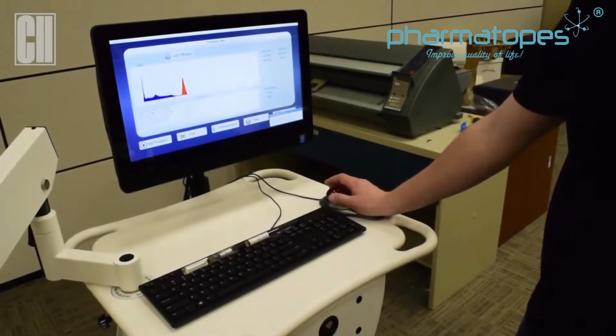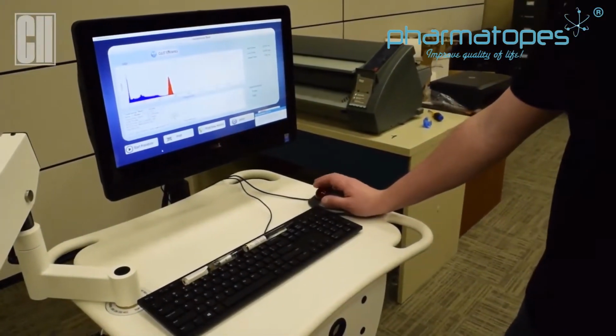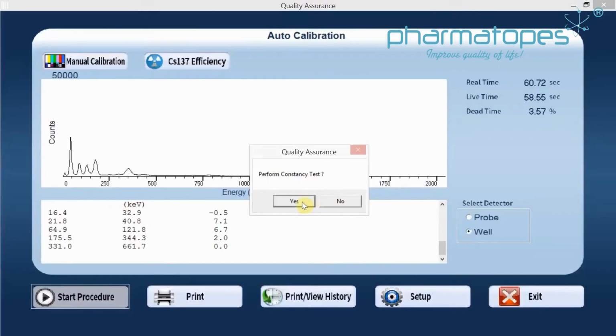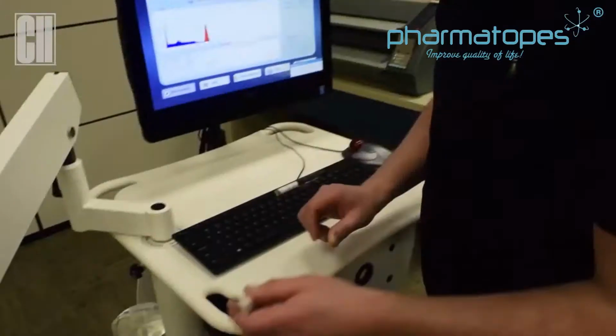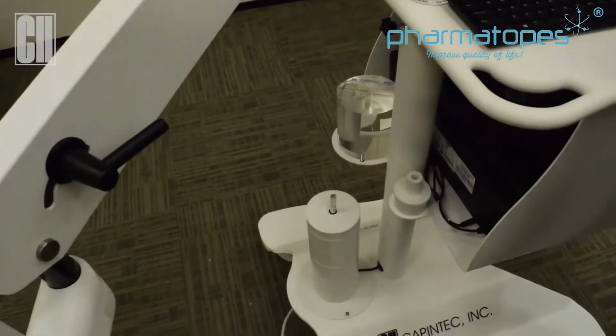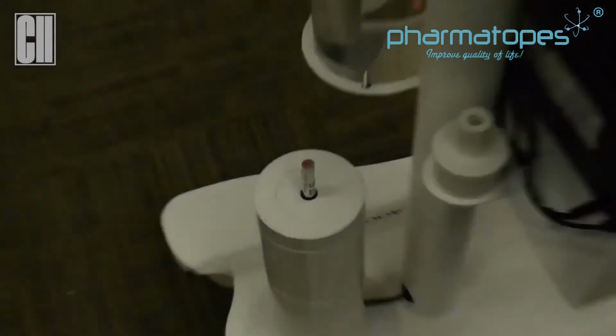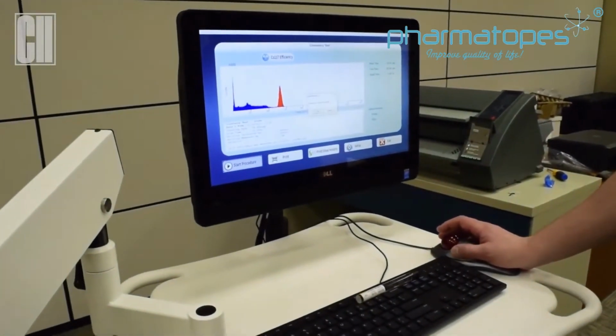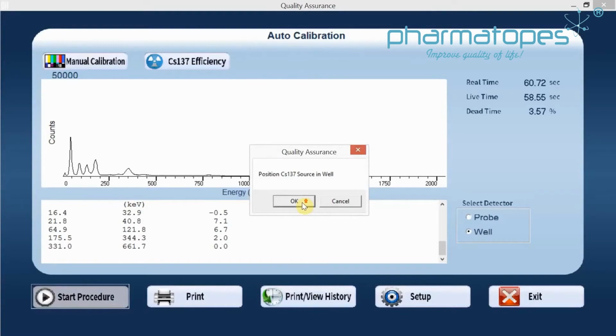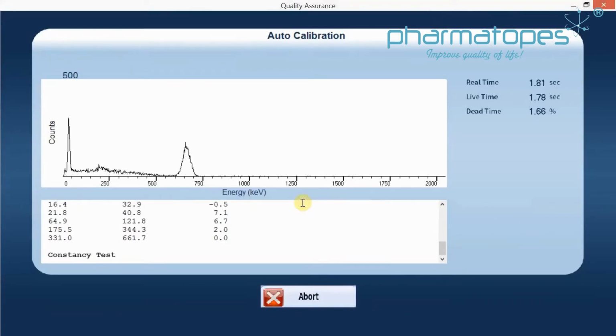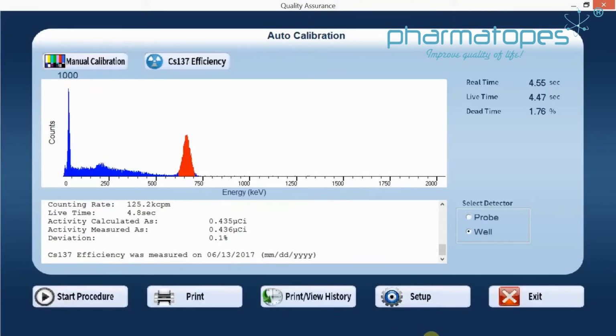Check the constancy for the well. So we click on start procedure, and now we position the cesium in the well. Once that's positioned, we'll click OK and perform the constancy. And then the result, it's completed. And now we're within our plus or minus 5%, so we're finished with the constancy check, and you can click on exit.